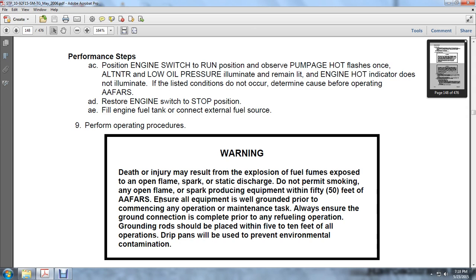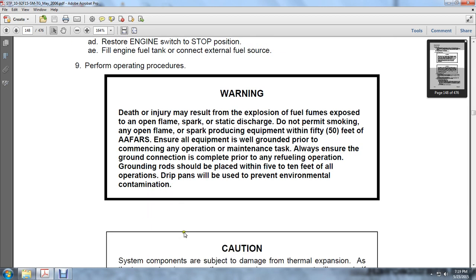fumes exposed to any open flame, spark, or static discharge. Do not permit smoking or open flame, or spark producing equipment within 50 feet of the advanced aviation forward area refueling system. Ensure all the equipment is well grounded prior to commencing any operation or maintenance task. Always ensure the ground connection is complete prior to any refueling operation. Grounding rods should be placed within 5 to 10 feet of all operations. Drip pans will be used to prevent environmental contamination.